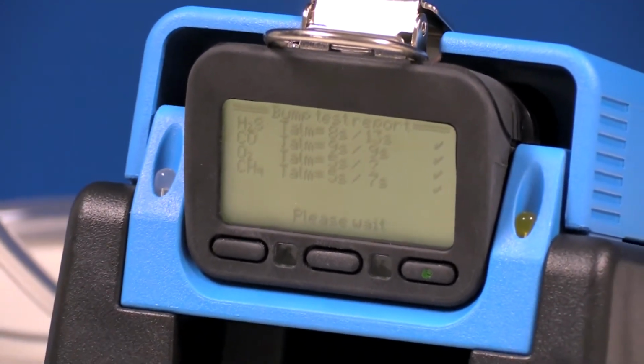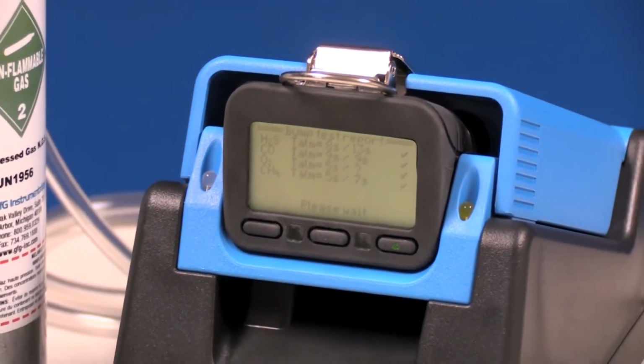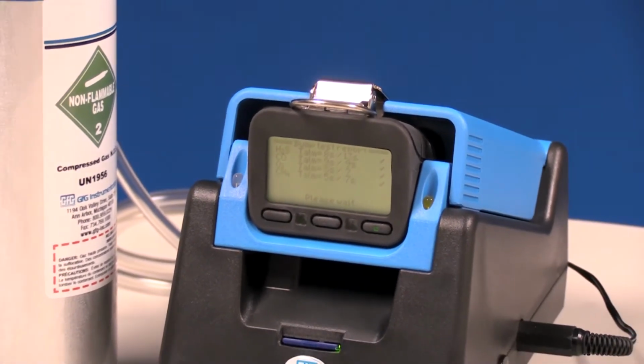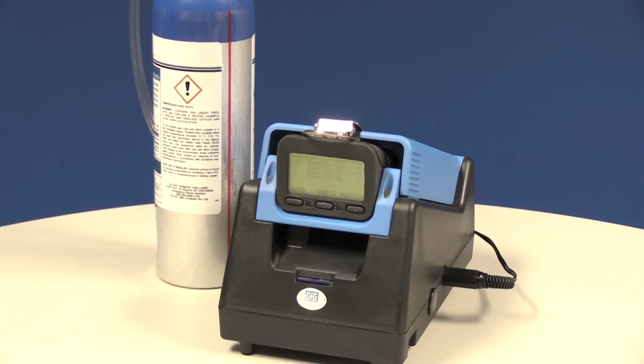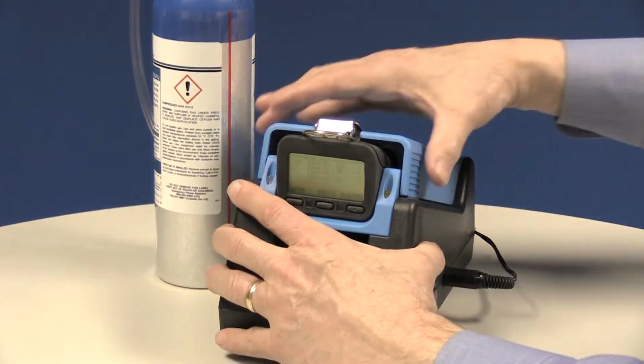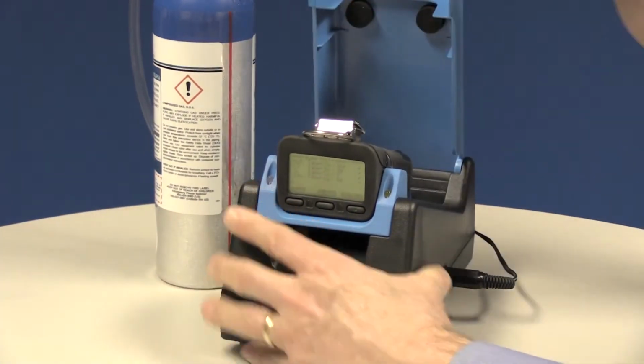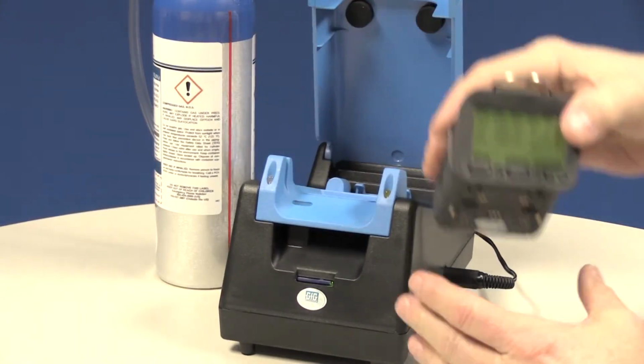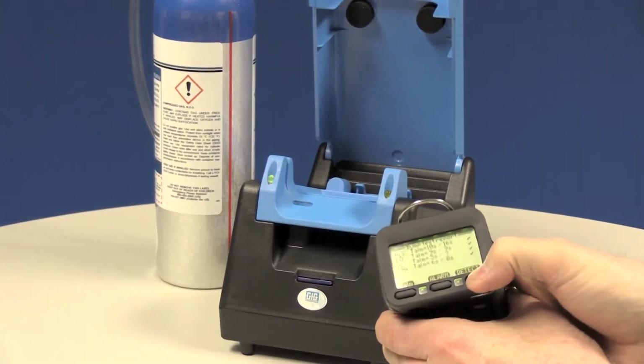All you need to do is insert the instrument into the cradle. The docking station will automatically perform the required procedure. The docking station takes less than 20 seconds to complete a bump test and uses less than 0.2 liters of calibration gas per test.